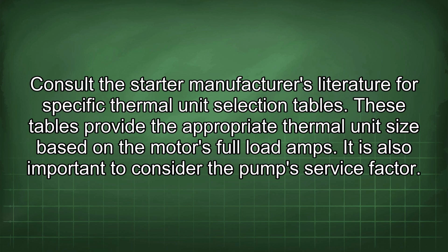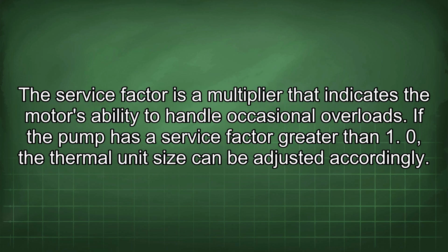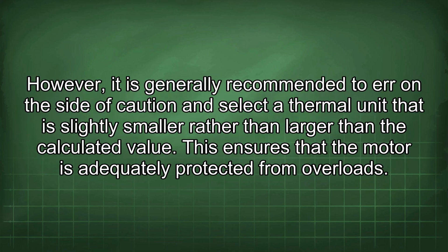It is also important to consider the pump's service factor. The service factor is a multiplier that indicates the motor's ability to handle occasional overloads. If the pump has a service factor greater than 1.0, the thermal unit size can be adjusted accordingly. However, it is generally recommended to err on the side of caution and select a thermal unit that is slightly smaller rather than larger than the calculated value. This ensures that the motor is adequately protected from overloads.